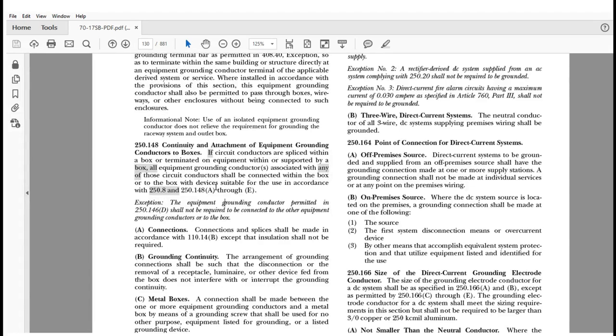So we need those EGCs, if you will, to commingle. Right? And people used to think that you did not, that you kept them separate for some reason. Remember, current only travels on that equipment grounding conductor where you have a ground fault condition, or one of the conductors faults out to something that is grounded, and that provides the path to allow the overcurrent protective device to recognize that sudden increase in current. Based on the rating of that overcurrent device, which can range from anywhere between 6 to 8 times its rating, it allows that current to surge and allows that overcurrent protective device to activate and clear that circuit. So it's very important to provide those paths.